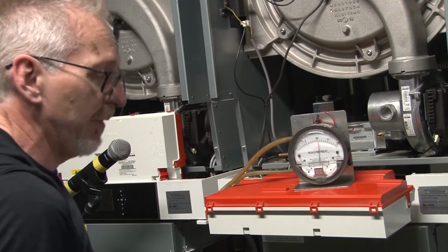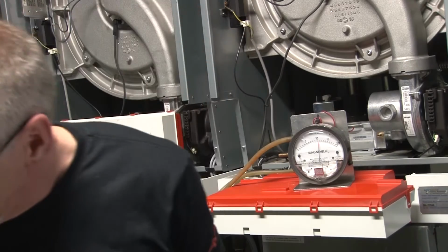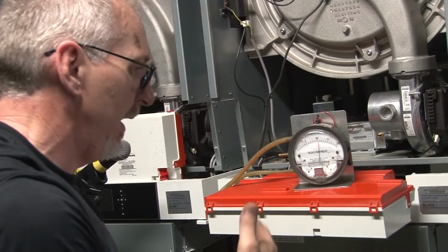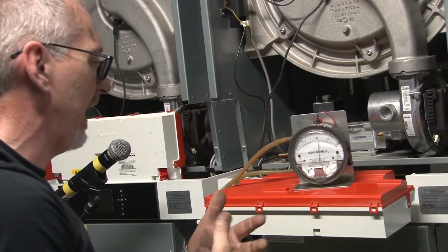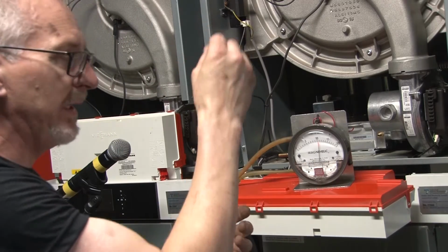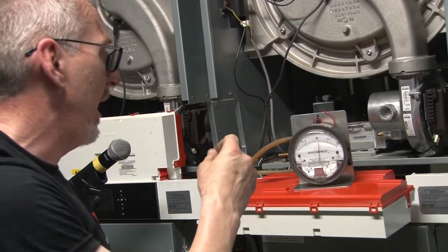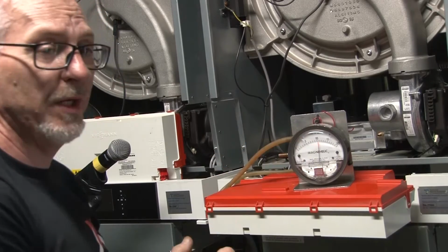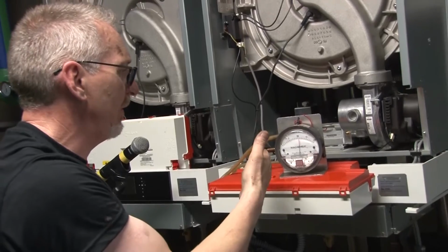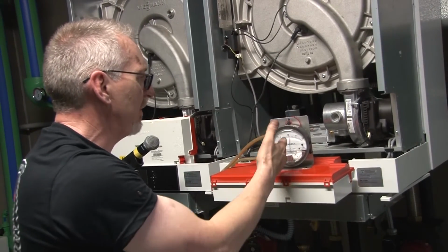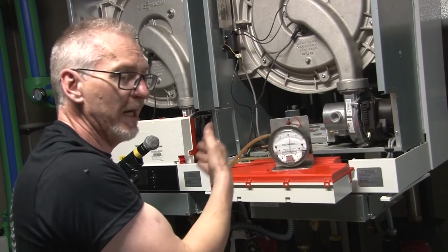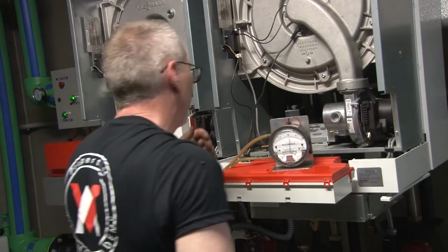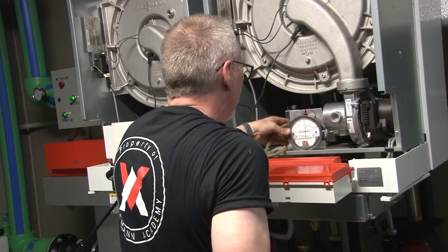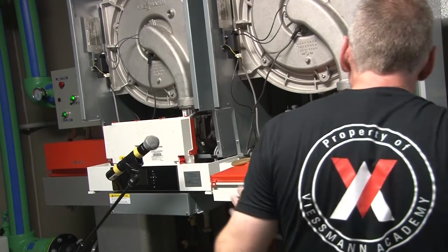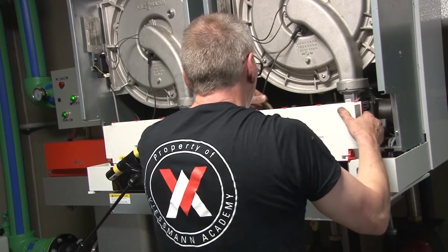That's what we call static pressure. So if I'm in the manual, I've got my maintenance manual there. In the documentation, you're going to have an area that you can mark the date you're doing your service, and you can also start recording this information. And it's important to record this stuff because year over year, if you start seeing changes here, it might be why you're having problems with the boiler. So it's important to document that. So there's your static pressure. And now we can turn the boiler on.